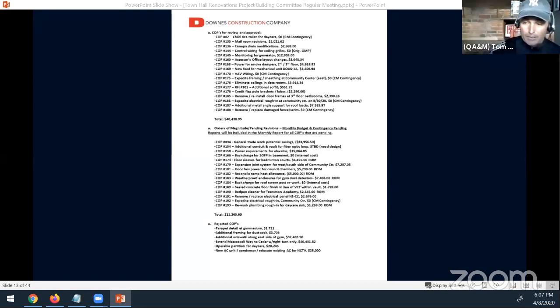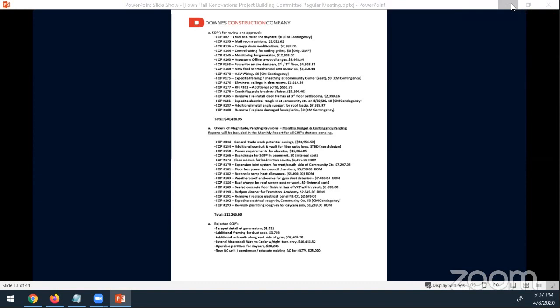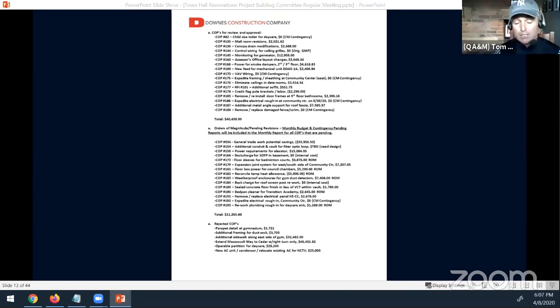Then we can identify if there's actual additional capacity. But from a calculation perspective, there was some concern that we were at 87% as opposed to the threshold of 82%. So we looked at the viability of taking the gym RTU off the generator.